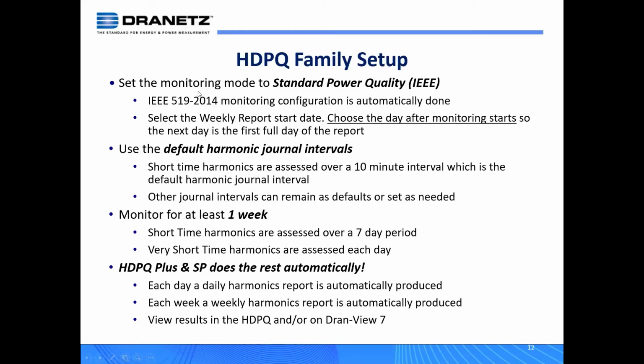As far as configurations for 519-2014, that's done automatically by the instrument. So you don't have to worry about anything. The instrument does everything for you as far as the configurations. The only other thing that you might want to consider is to select the weekly report start date and choose the day after the monitoring starts. And what we mean by that is that today is Wednesday. If I start monitoring today, I want to choose Thursday as the start of my reporting.